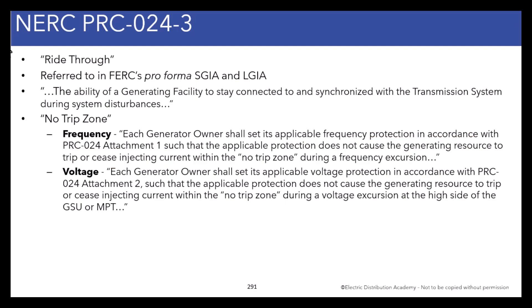The same applies to voltage. Voltage is a local phenomenon, meaning it can have different values at different buses or points on the system that are relatively close together. Frequency, by contrast, stays the same across an entire interconnection — whether you're in Southern California or Northern Washington, the frequency is the same. Because voltage is local, the standard had to define where the voltage excursion actually occurs: at the high side of the generator step-up or main power transformer.